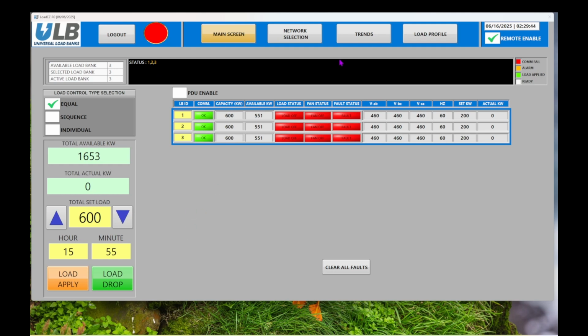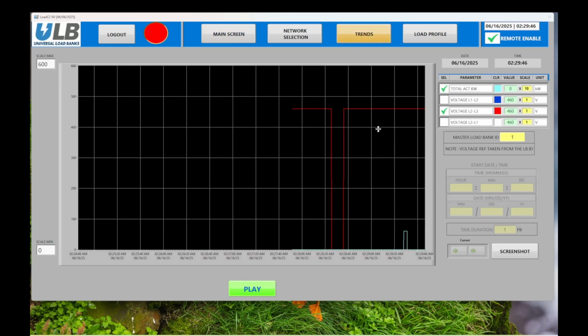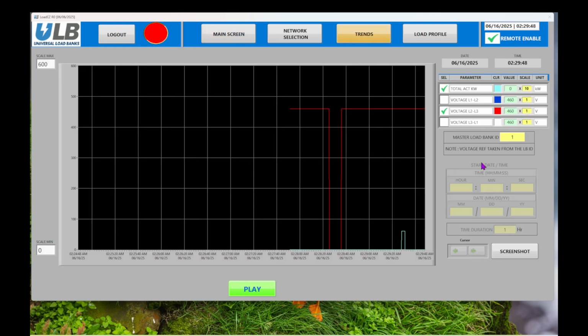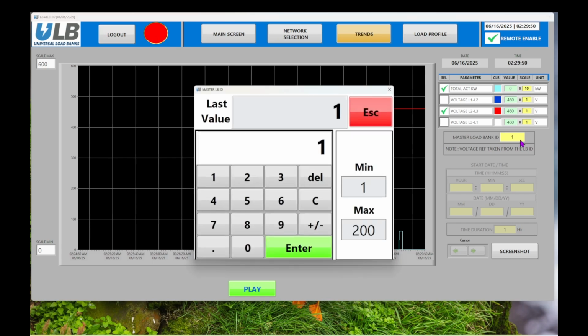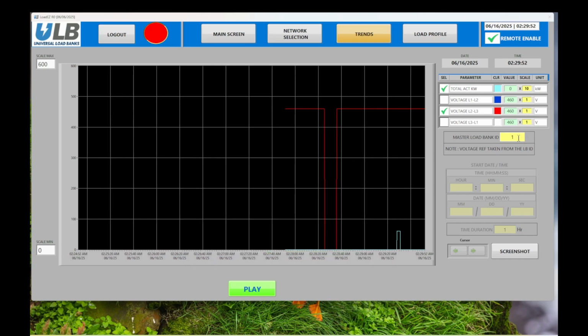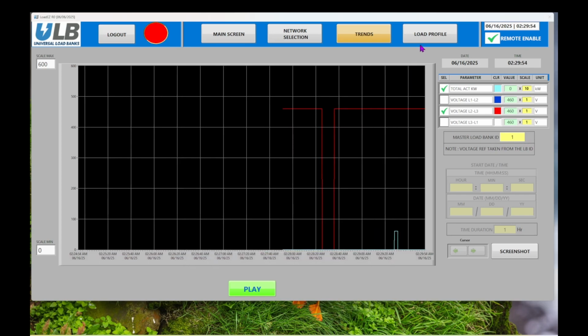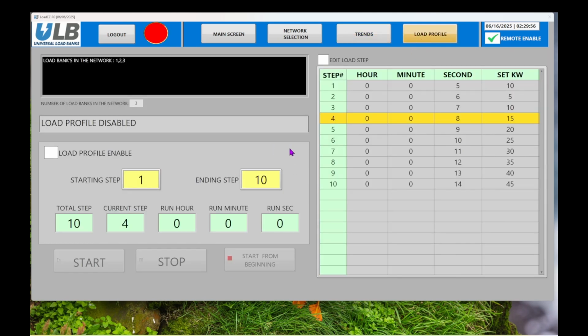The trend screen works just like in single load bank mode. Ensure the master load bank ID is configured to display the reference voltage correctly in the trend chart. Load profile management also works the same way. The only difference is that it now applies based on the selected mode, equal or sequence.